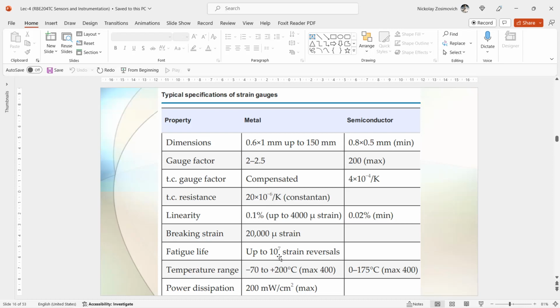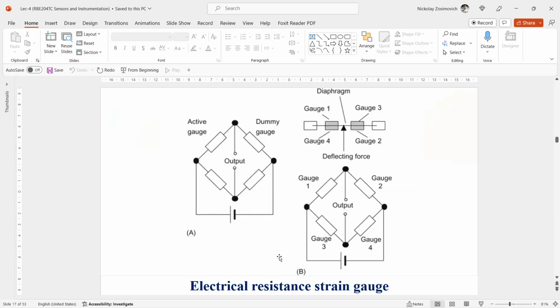provoked by temperature variation. The effect on resistivity is minimized by a proper material choice for the strain gauge wire, for instance, constantan. This is an alloy of copper and nickel called constantan, with a low temperature coefficient. Residual temperature effects due to a non-zero temperature coefficient are further reduced by a proper interface. So, to compensate for thermal expansion, manufacturers supply gauges that can be matched to the material on which the gauges are mounted. These are so-called matched gauges.